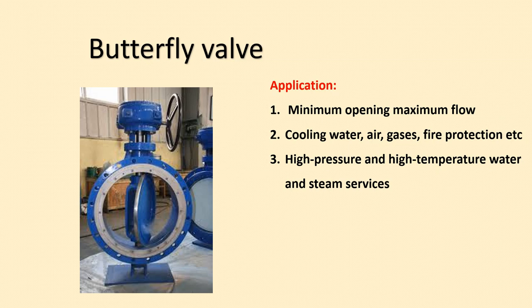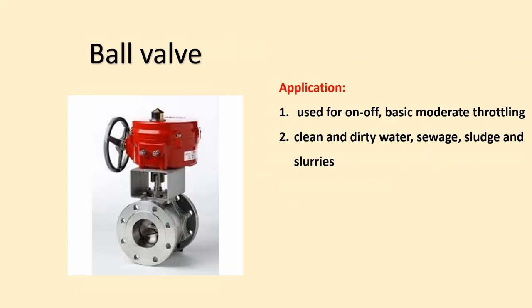Next is the butterfly valve. The main application is that for a minimum opening it offers maximum flow — within 20 to 30 percent of valve opening, nearly 90 percent of flow is established. The butterfly valve is widely used in cooling water lines, process gas, and fire protection piping because of its advantage of minimum opening with maximum flow. It can also be used in high pressure, high temperature water and steam services. During any fail-safe condition in the plant, the butterfly valve can open immediately to provide cooling or venting services.